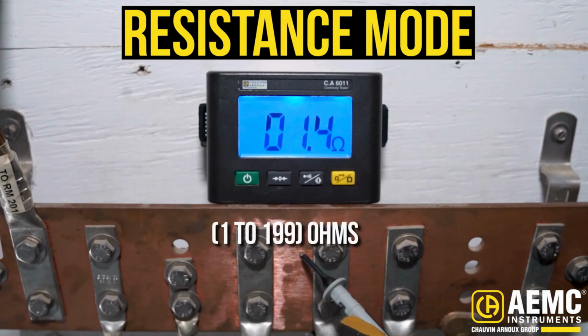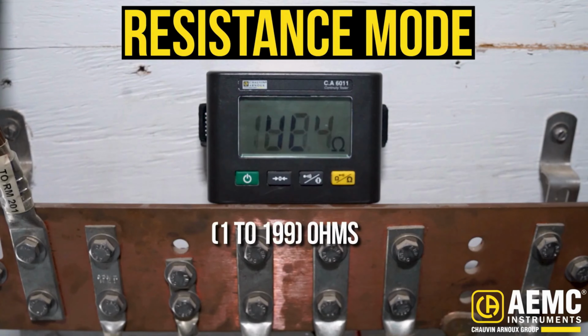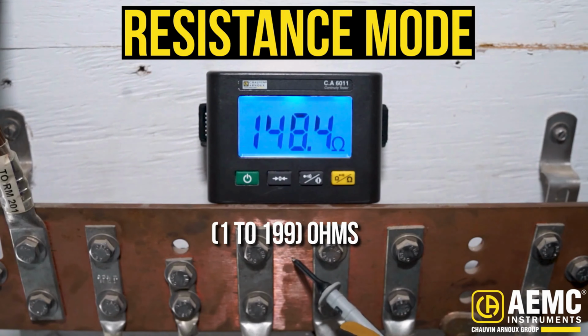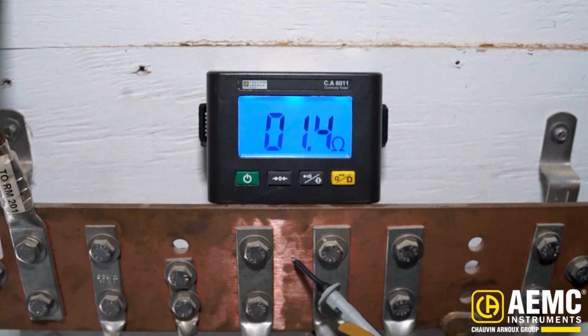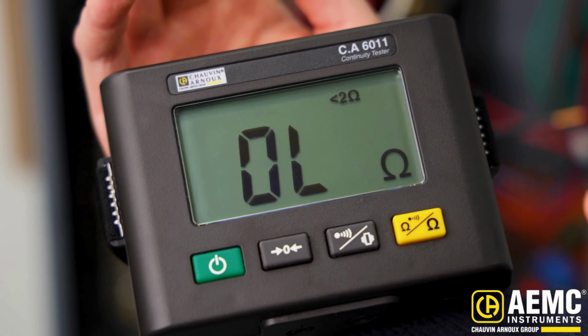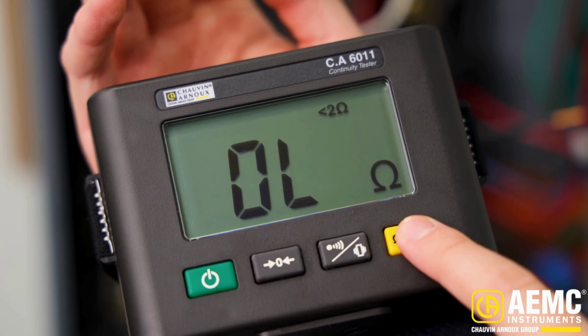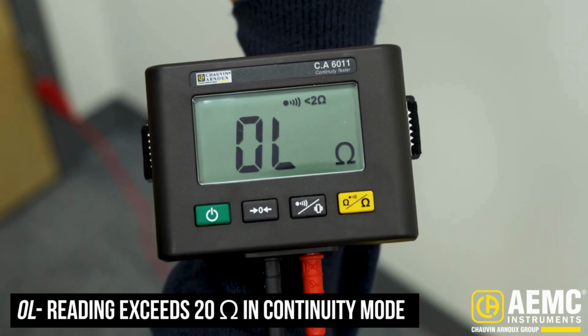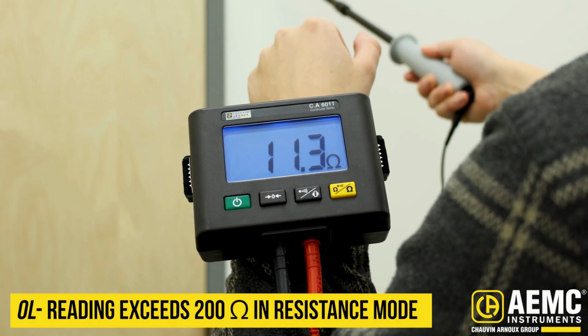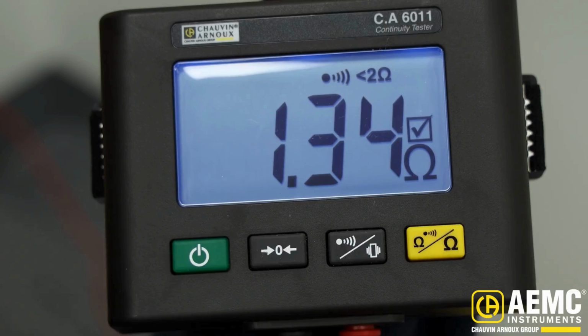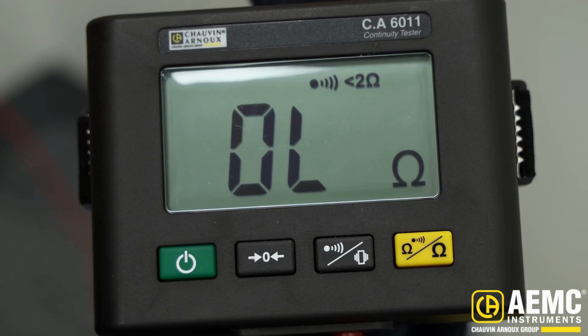When you don't need a full continuity test, switch to resistance mode. Here, the CA6011 measures from 1 to 199 ohms, ideal for general resistance and connection checks. In both modes, the instrument automatically displays OL when the reading exceeds 20 ohms in continuity or 200 ohms in resistance, so you know when a connection is out of spec or open.